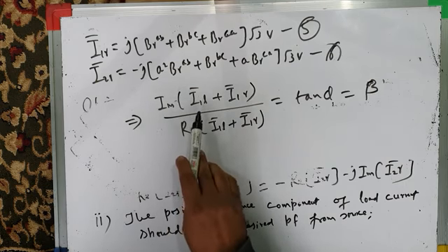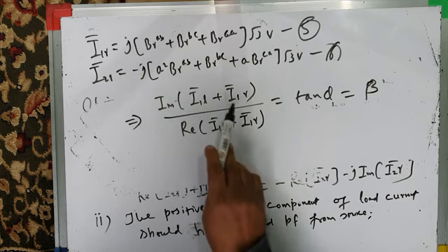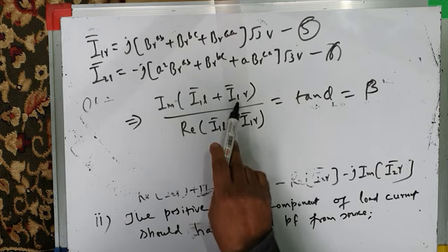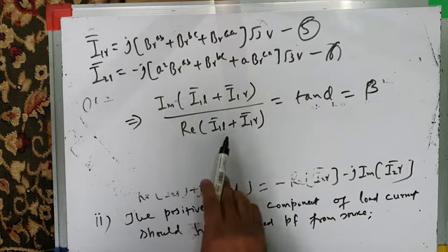Imaginary part, see, now you have two currents there. Load has the positive sequence of load current, plus there is positive sequence of compensator current also, divided by the real part. So this divided by this should be equal to the desired power factor, that is tan phi, that is equal to beta. Okay, so that means, from here, if you take out the imaginary part of I1L plus I1 gamma, that is equal to beta times the real part of I1L plus I1 gamma.